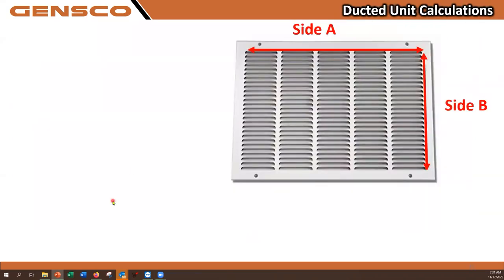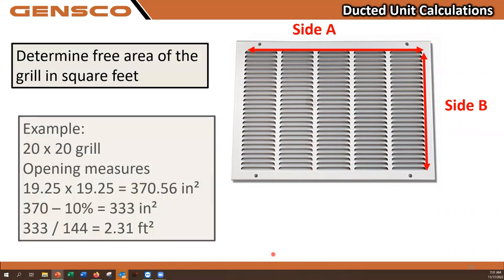So how do we measure the air? First, we need to know the actual opening of the grill. We'll take side A and multiply it times side B. And this is, for an example, a 20 by 20 grill, but it doesn't have an opening 20 by 20. The actual inside opening of this grill is going to be 19.25 by 19.25. Yours may be slightly different. You could have 19.5 by 19.5, but you get the message. It's the actual inside opening. So I've got an actual opening of 19.25 by 19.25.